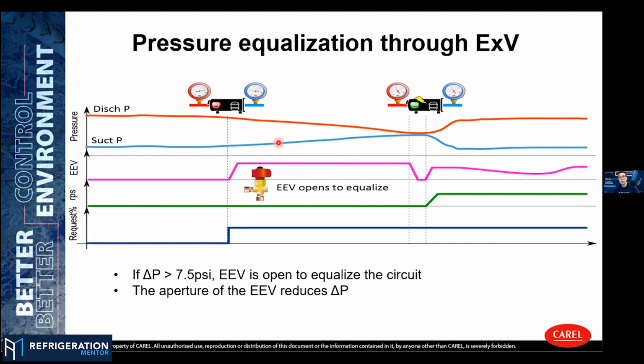Yeah. That makes a huge difference when you equalize the pressure, because just like you said, you can try this out in the field before a system starts up. Put your amp clamp on and see what it does when it starts up, and you can tell if the pressures are equalized or not.